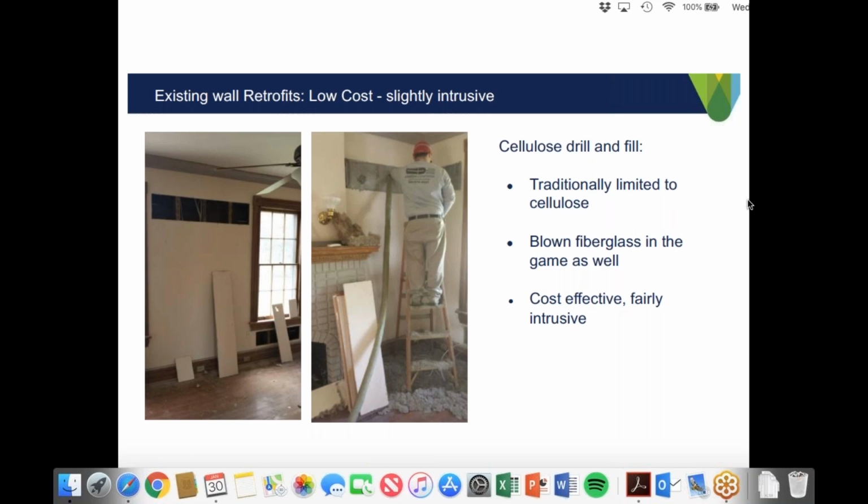Before all these projects, this is probably one of the ones I'm most proud of. We blower door tested before we went in, and we were completely unable to depressurize the home. It was estimating probably about 12,000 CFM of leakage, which is extremely high. After the work scope, we brought the attic into conditioned space, conditioned the crawl space, and then re-insulated every wall cavity with cellulose insulation. By doing so, we were able to drop the number to 4,000. So quite a big jump there.